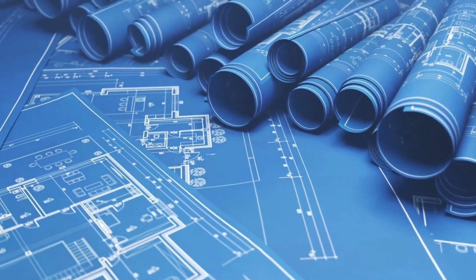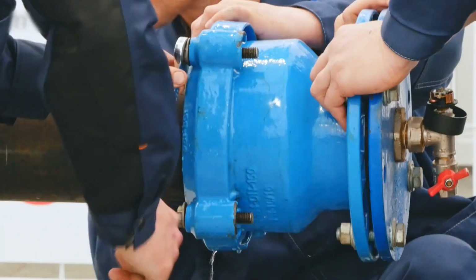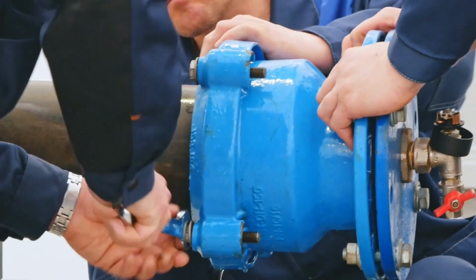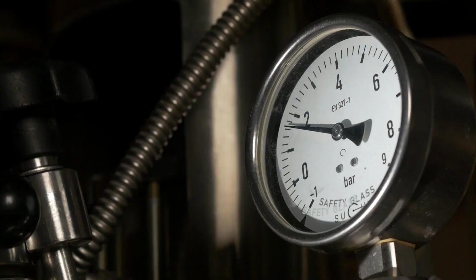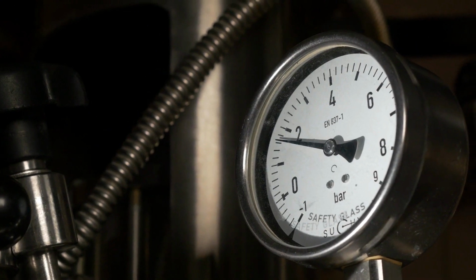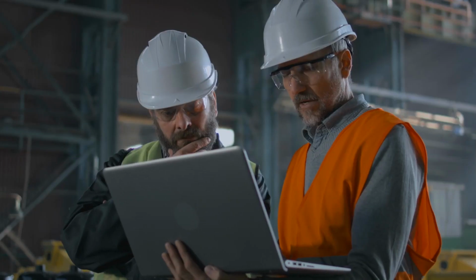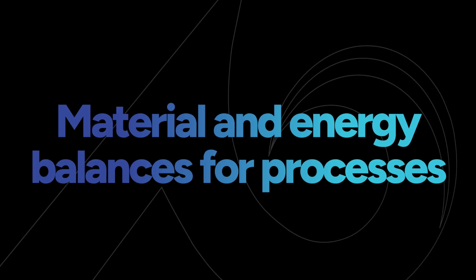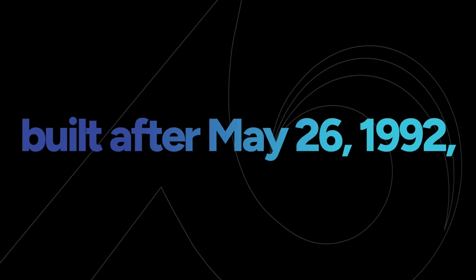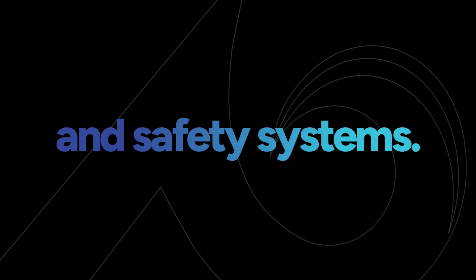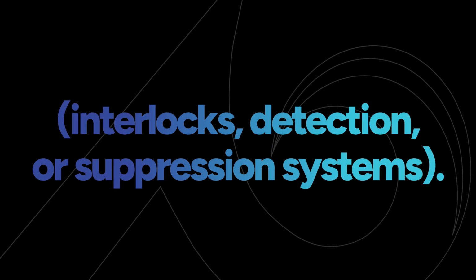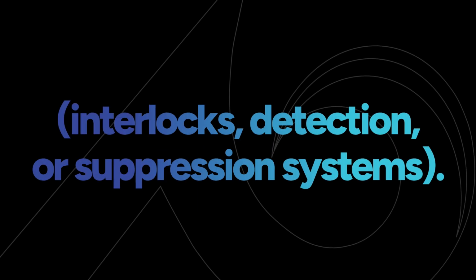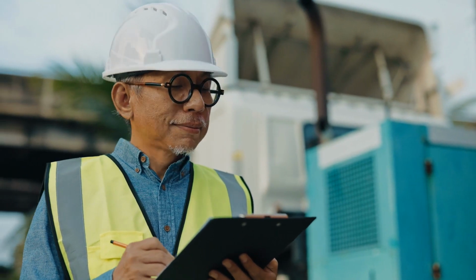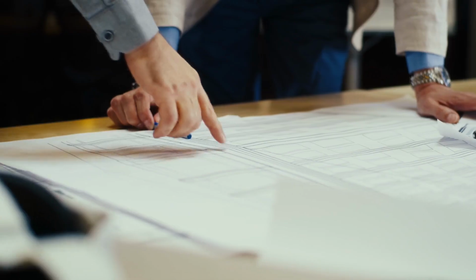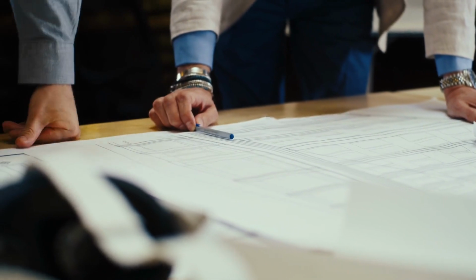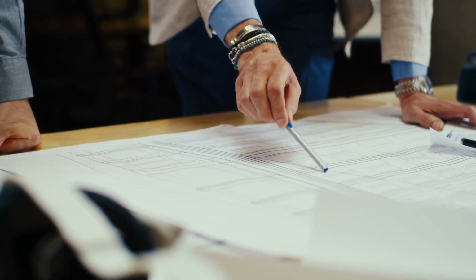Information on the equipment used must include materials of construction, piping and instrument diagrams, P&IDs, electrical classification, relief system design and design basis, ventilation system design, design codes and standards employed, material and energy balances for processes built after May 26, 1992, and safety systems, for example, interlocks, detection, or suppression systems. Your employer must document that equipment conforms with recognized good engineering practices. OSHA provides alternative methods to accomplish this when equipment was designed according to earlier practices and requirements.